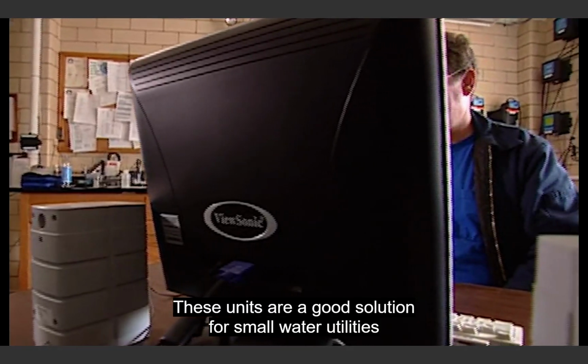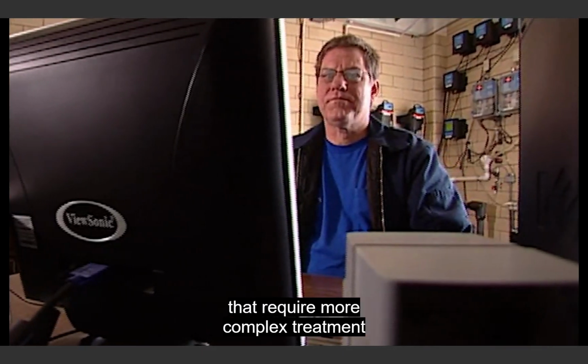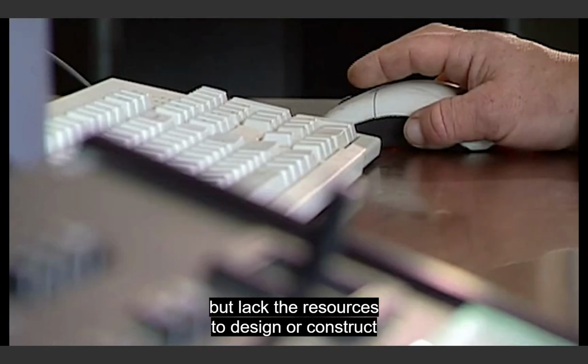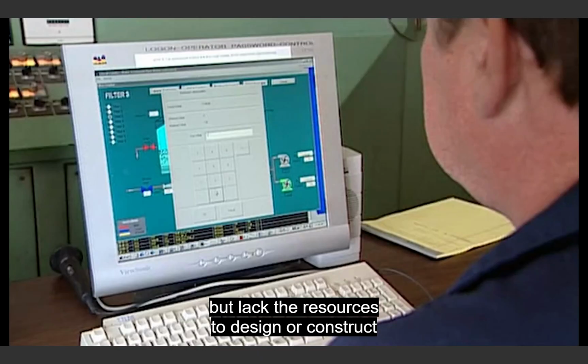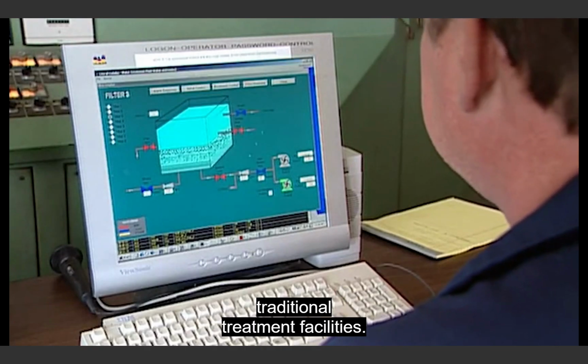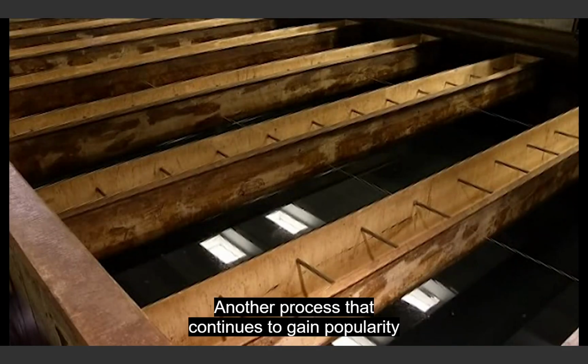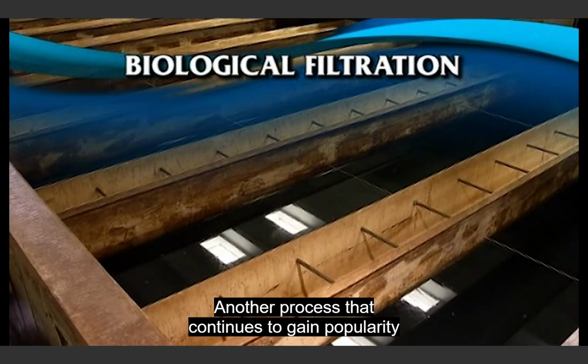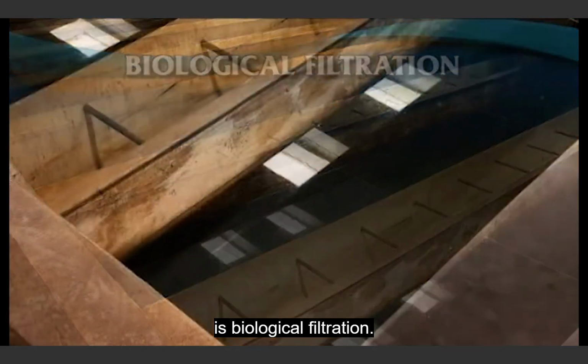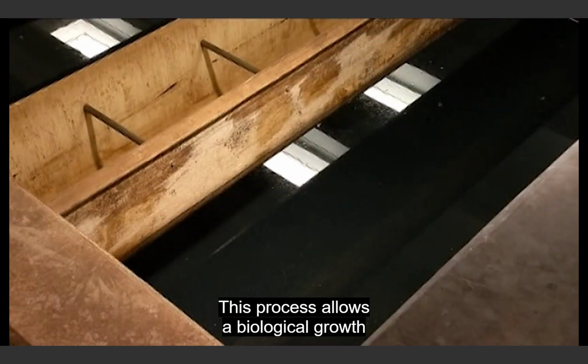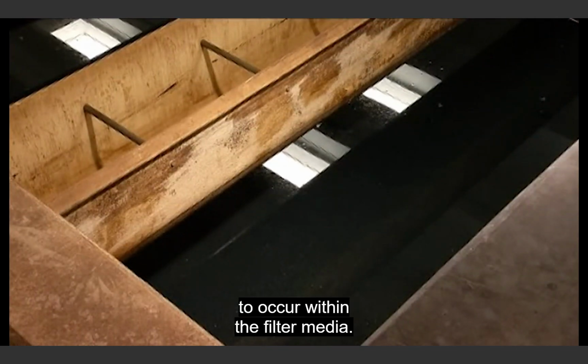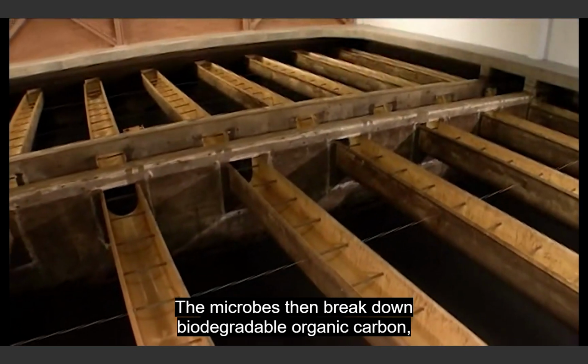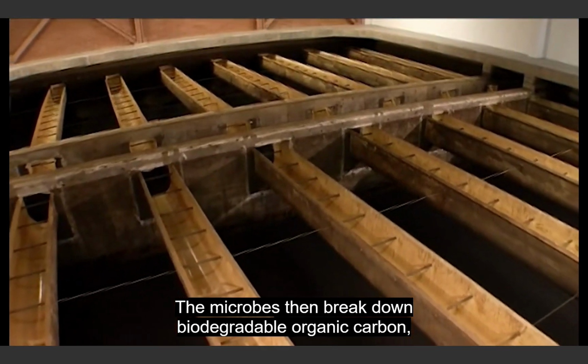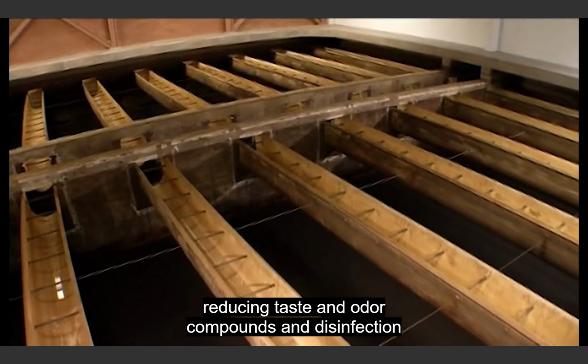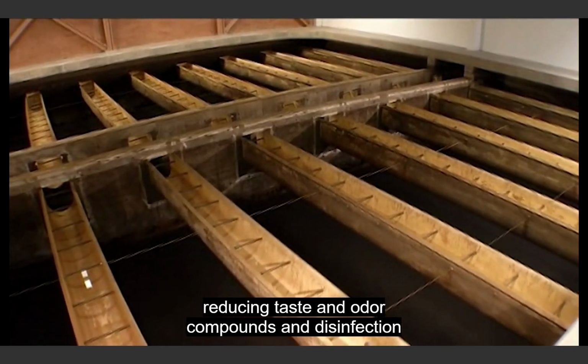These units are a good solution for small water utilities that require more complex treatment but lack the resources to design or construct traditional treatment facilities. Another process that continues to gain popularity is biological filtration. This process allows a biological growth to occur within the filter media. The microbes then break down biodegradable organic carbon, reducing taste and odor compounds and disinfection byproducts.